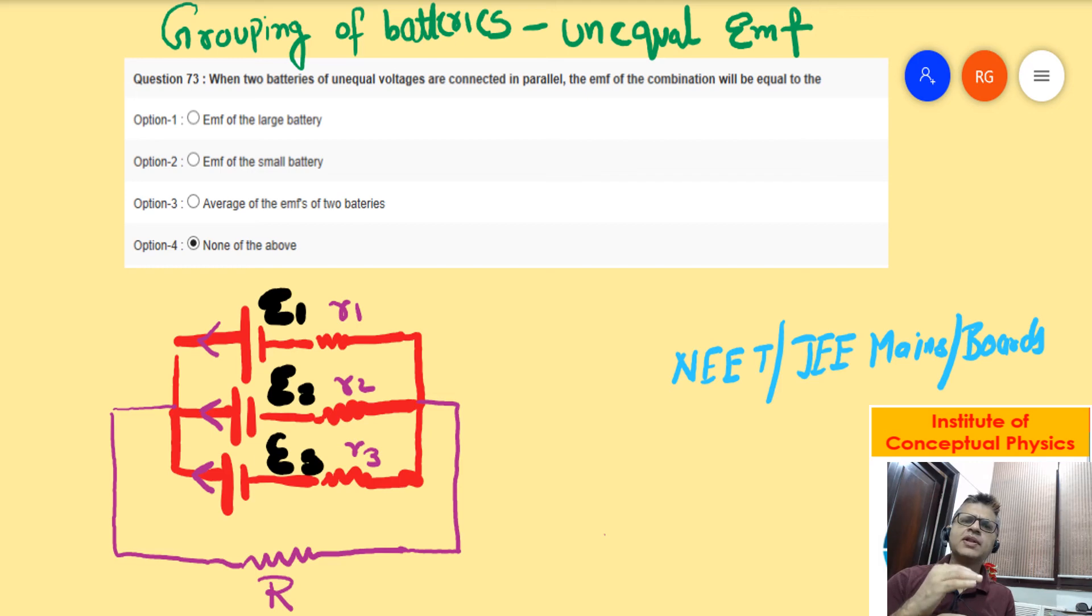But the point I want to make is if you connect batteries of unequal EMF, there is a complete derivation of the equivalent EMF of this system, though this arrangement is not recommended. What is recommended is parallel batteries of equal EMF only. Unequal EMF is not recommended. Thank you very much.